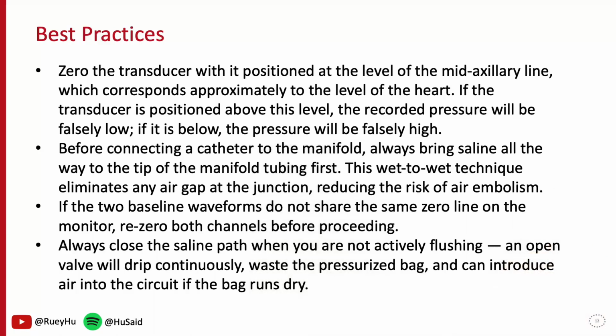So before we finish, I wanted to go over some best practices. Make sure you zero the transducer with it positioned at the level of the mid-axillary line, which corresponds to approximately the level of the heart. If the transducer is positioned above this level, the recorded pressure will be falsely low. If it is below, the pressure will be falsely high. Next, before connecting a catheter to the manifold, always bring saline all the way to the tip of the manifold tubing first. This wet-to-wet technique eliminates any air gap at the junction, reducing the risk of air embolism. If the 2 baseline waveforms do not share the same zero line on the monitor, re-zero both channels before proceeding.